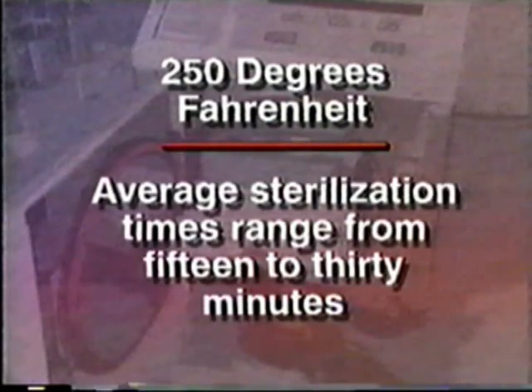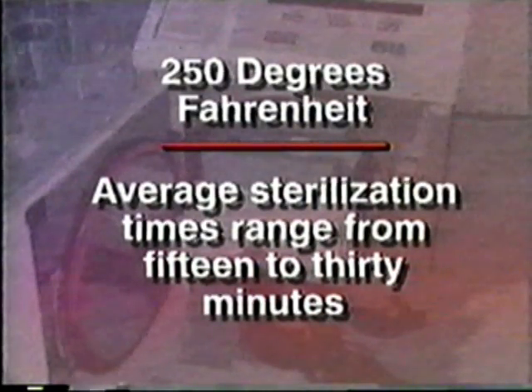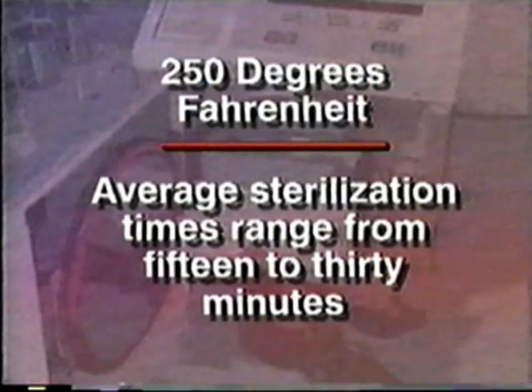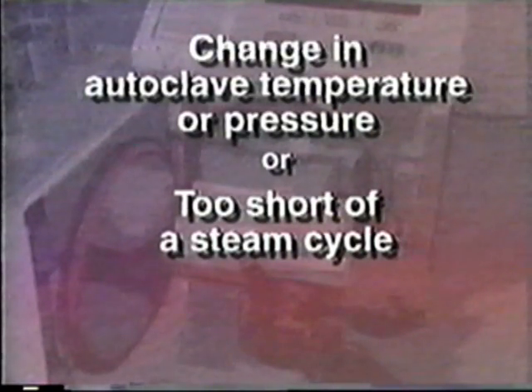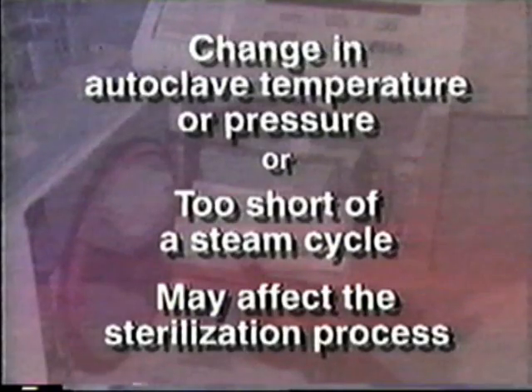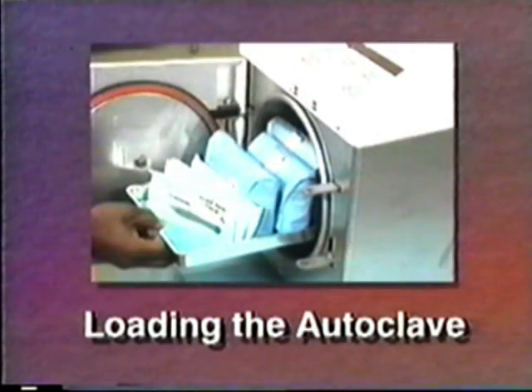An autoclave sterilizes by heated steam pressure, usually at 250 degrees Fahrenheit. Length of sterilization time varies according to the item and whether the wrapper is made of paper or fabric. At 250 degrees Fahrenheit, average sterilization times range from 15 minutes for unwrapped items to 20 or 30 minutes for wrapped items. It is important to remember that a change in autoclave temperature or pressure, or too short of a steam cycle, may affect the sterilization process.